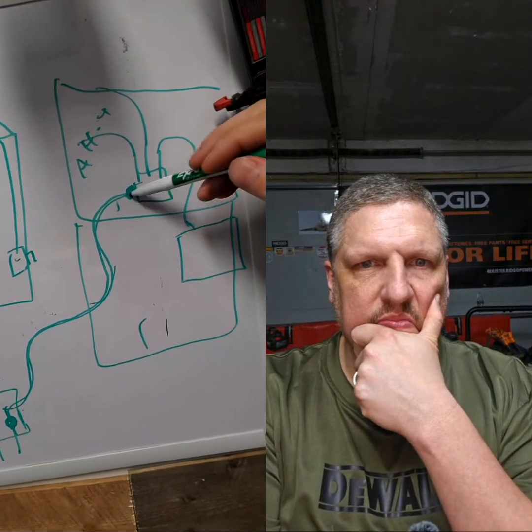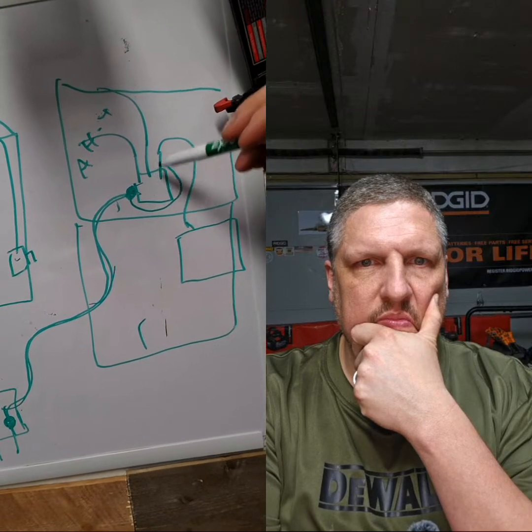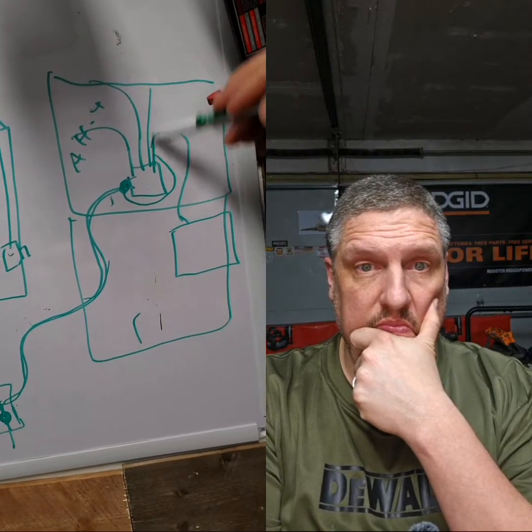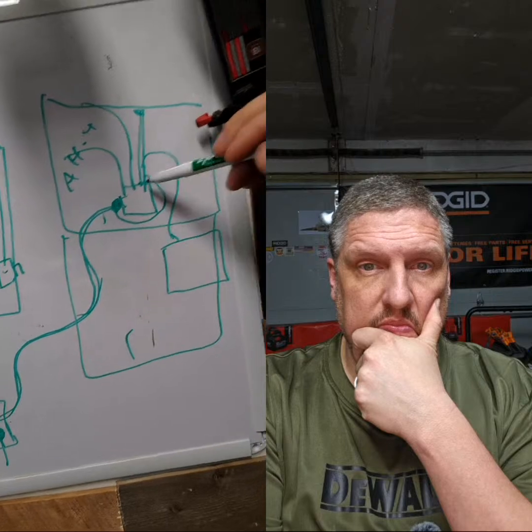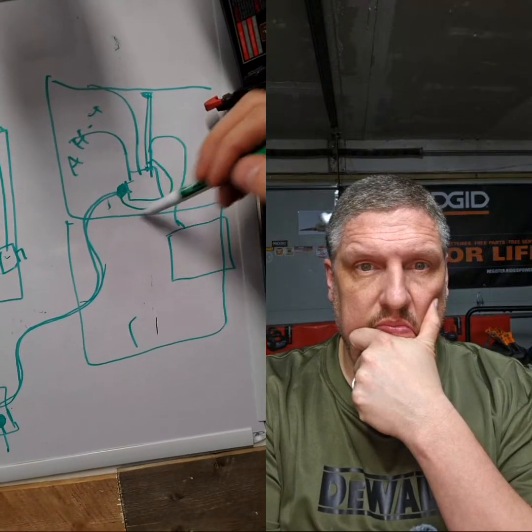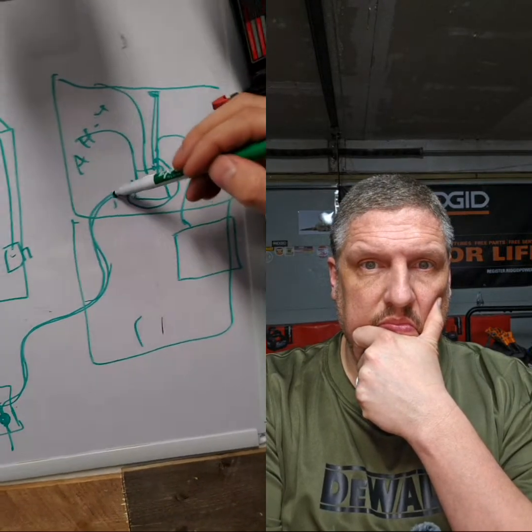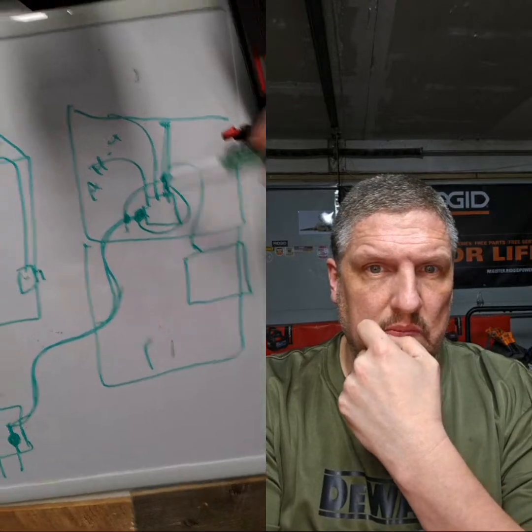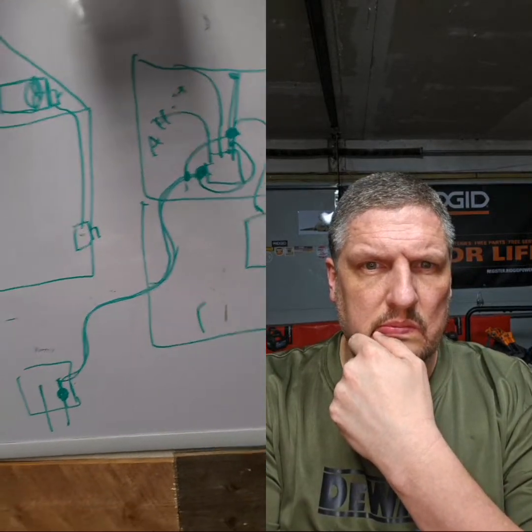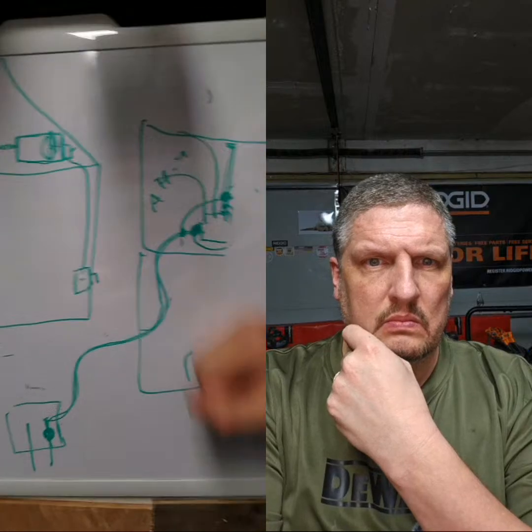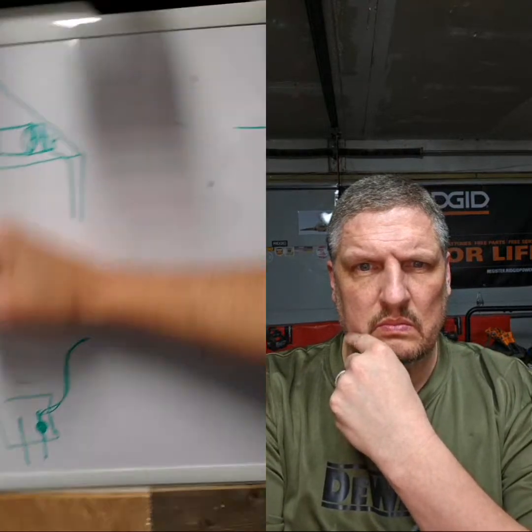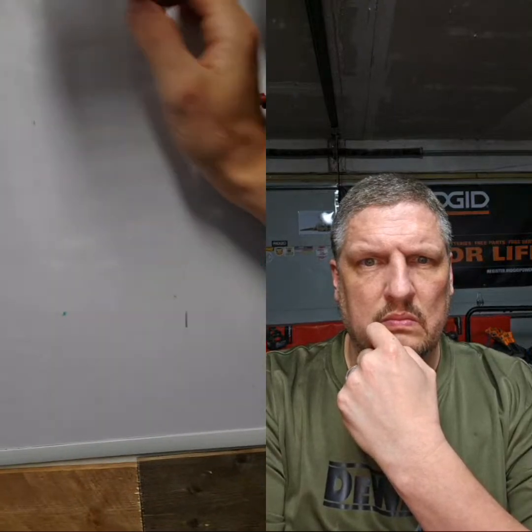And if you need to, you can jumper. So if you went from the manifold with black pipe or whatever, and you're questioning this manifold being conductive, you could jumper from here to there. We got a lot of lines going on now, but that's kind of it in a nutshell, right? Do you need to bond the gas? The code says yes. Should you? I don't know.